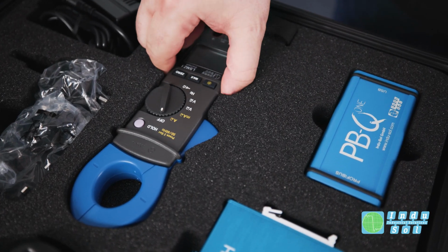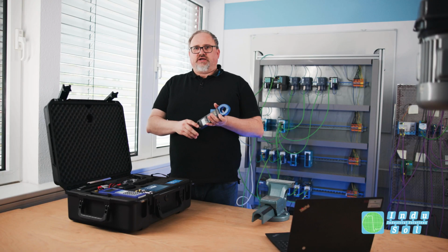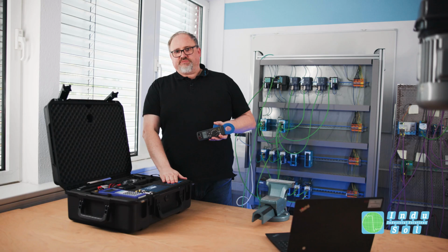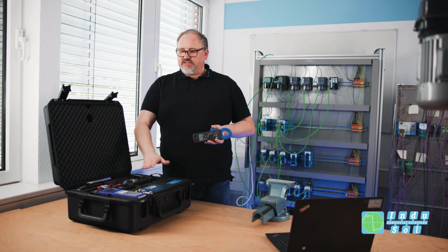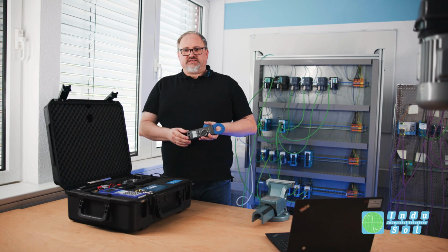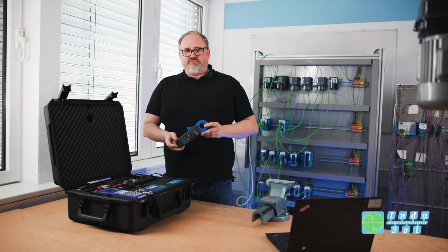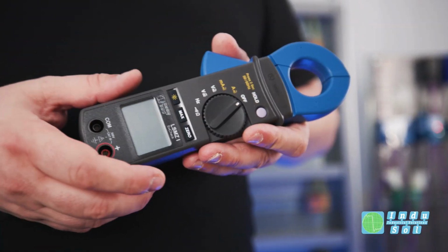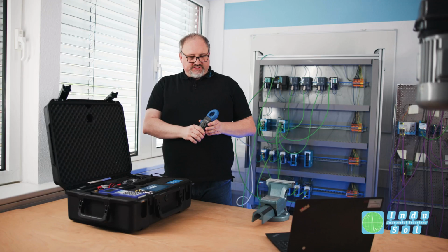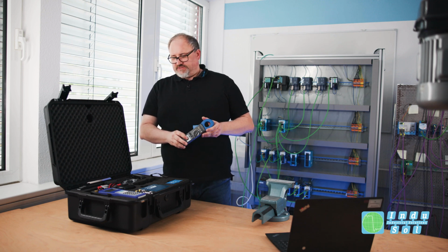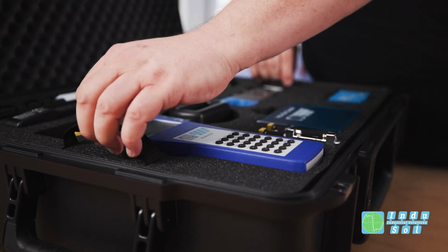The last tool would then be the leakage current clamp meter. Yes, it can happen. You have conducted all the analysis, you have measured with the PB-Q and actually saw good values in the bar. You conducted the line test, and here too there were good values. And now there is one last possibility, and that is the famous EMC issue. That means currents that, for example, flow over the shielding. To find this out, there is this current clamp, which is relatively well insulated and can show you the alternating current components on your wiring. So now I have introduced the tools to you.